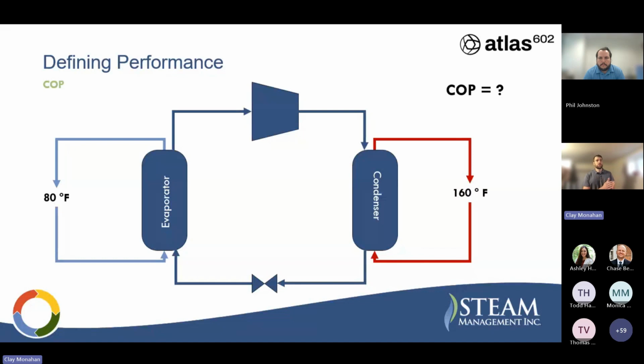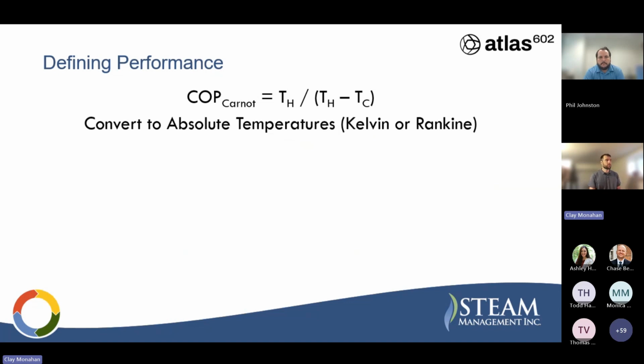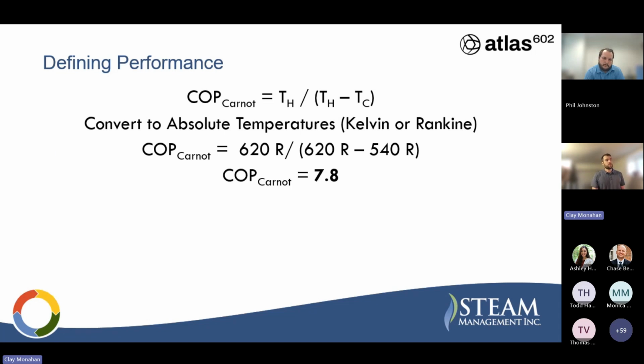So for this system, just theoretically, let's start with our base COP case. We have an 80 degree F heat source and a 160 degree F heat sink. So let's do the quick theoretical calculation. That theoretical maximum, the COP Carnot, is the hot temperature divided by the temperature delta. You do have to convert to absolute temperature units, whether that be Kelvin or Rankine. And for any European colleagues on here, apologies for doing this in Rankine, but if we have 620 divided by the temperature delta of 620 minus 540, that's going to yield us a COP of 7.8. Before we move on to seeing the effect of the actual versus the theoretical maximum, let's go into a few examples to see how temperature influences this maximum COP.